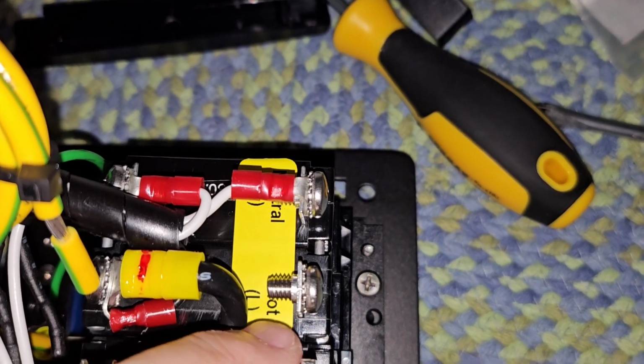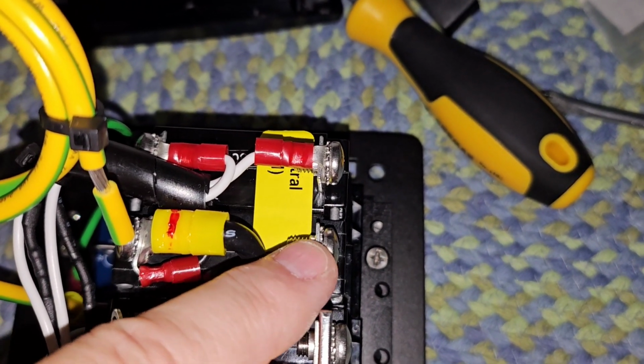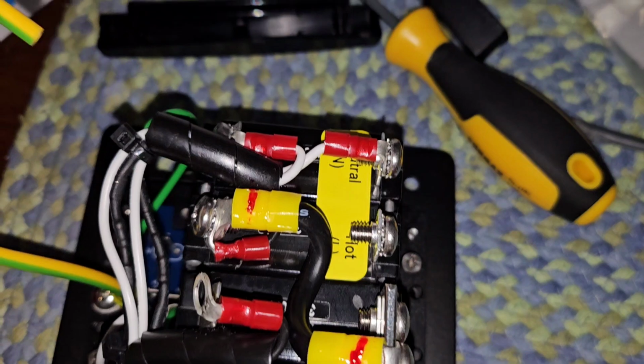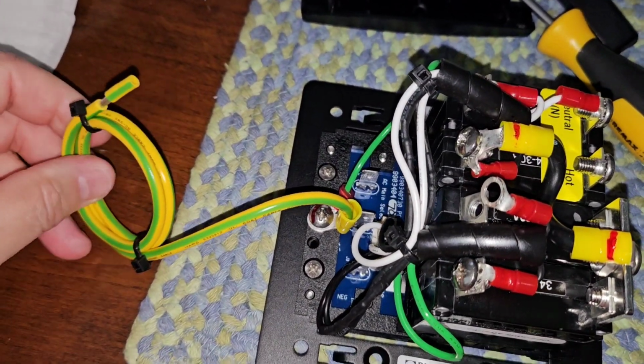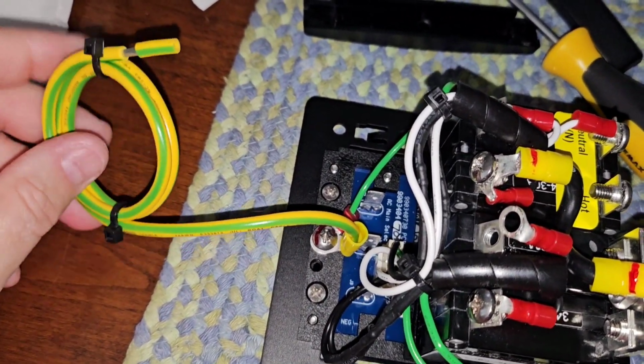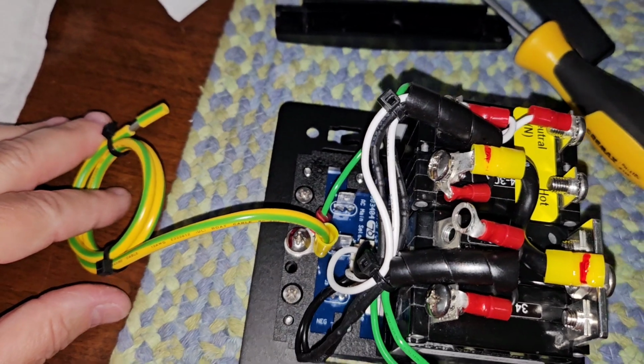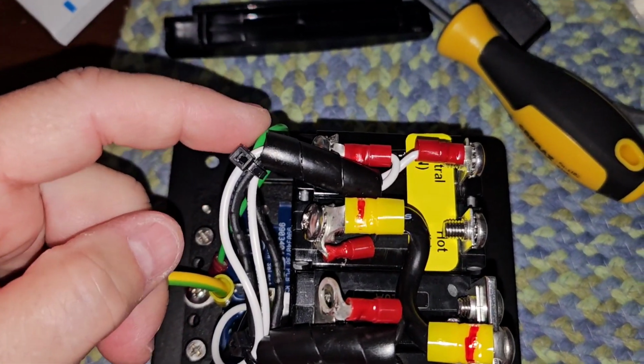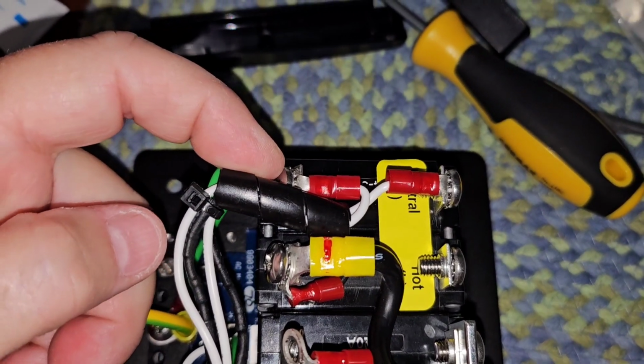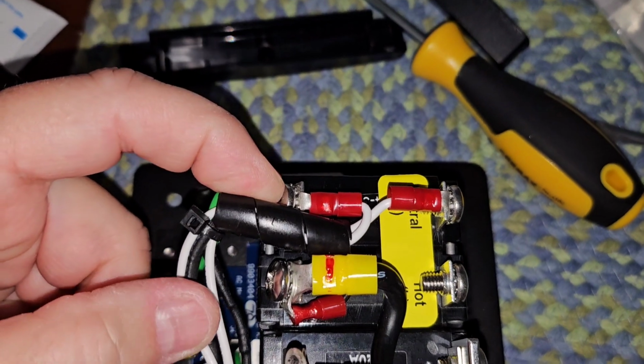and this is the hot or black wire connection of the AC output. Then this wire here is the ground, and it's going to go to a bus bar just for the ground. And then I have to come off of this neutral for a neutral ground bar.